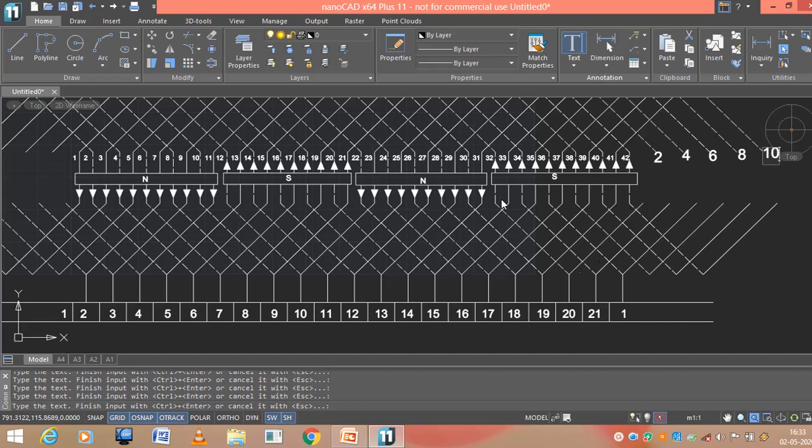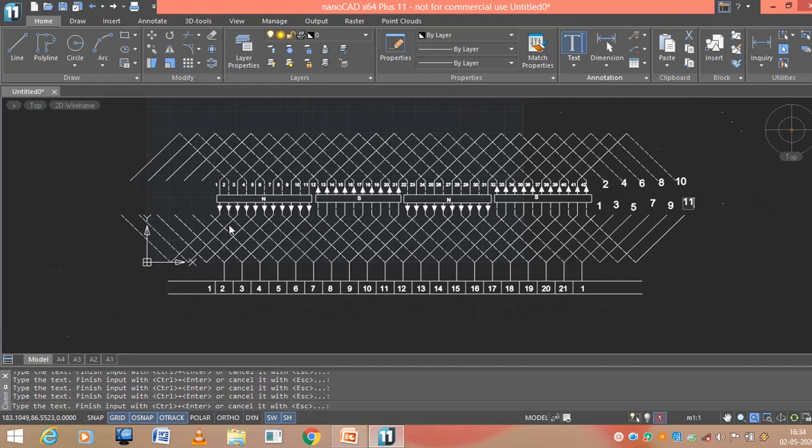Likewise, you can trace this. This is 32. 32 plus 11 is what? 32 plus 11 is 43. 43 means it should be connected to conductor 1. This is conductor 3, 5, 7, 9 and then 11. Likewise here also the first conductor is connected to 32. It means the first conductor should be connected to here, it is 32. If this is 32, this should be 34, 36, 38, 40 and 42.